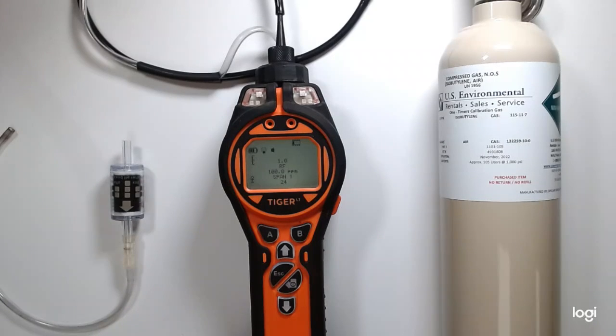I would also like to note that when calibrating any of these PIDs, it is good to start them and let them run for a few minutes prior to your actual calibration. It's good to have the lamp warm up and the sensors warm up before you actually go ahead and push a calibration.